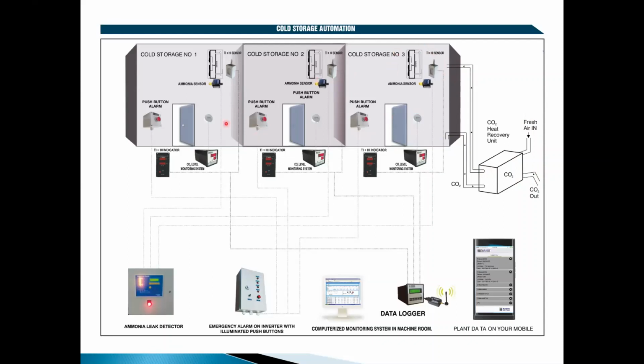Then we have the cold room alarms, or what we call the man trap alarms. In case a person is trapped in the cold room and cannot open the door from inside, he can use this switch, an illuminated push button provided inside. You push this switch and you get a centralized audio and visual alarm, with inbuilt battery backup. So a person in the plant room can understand that somebody is trapped in a cold room.